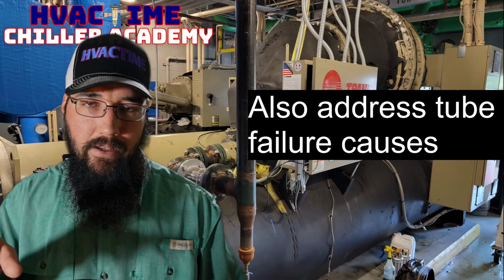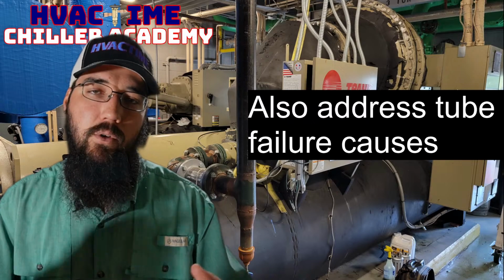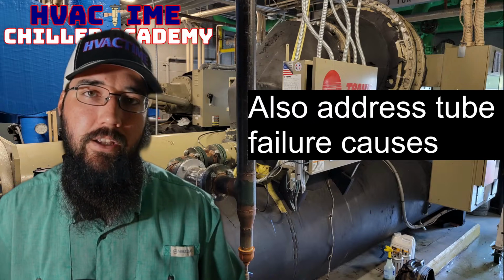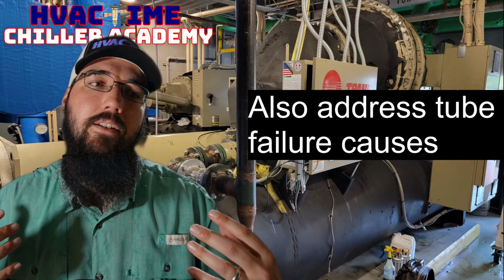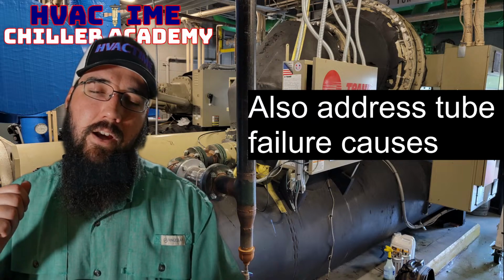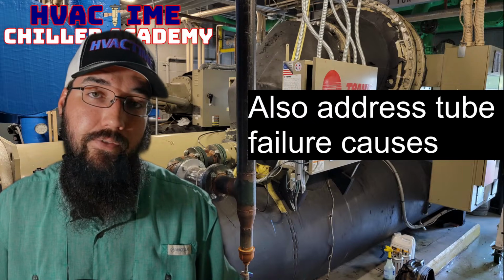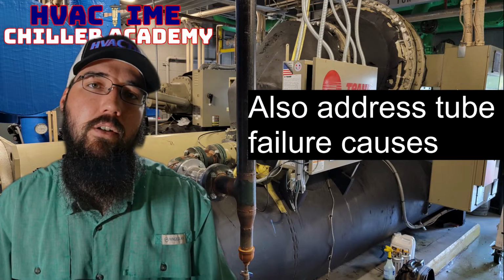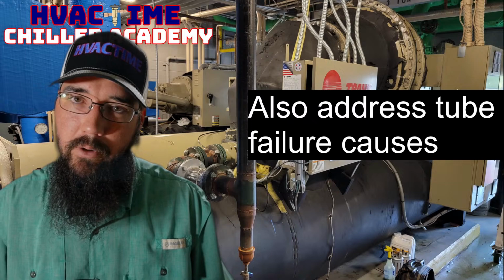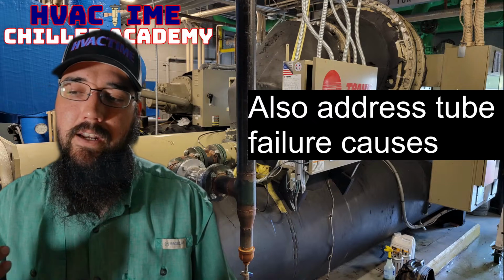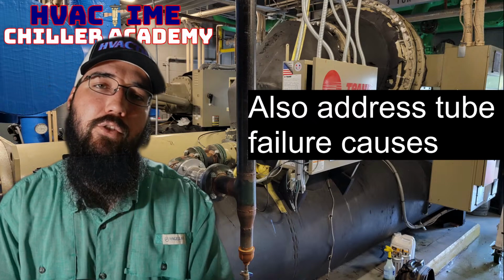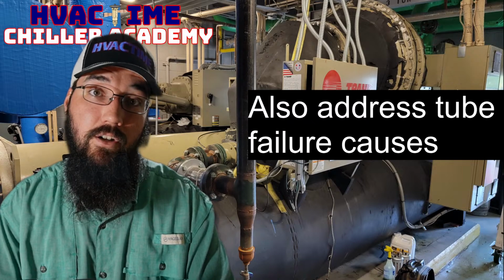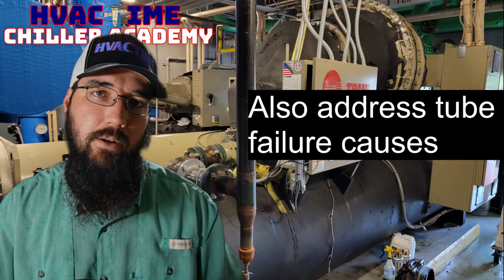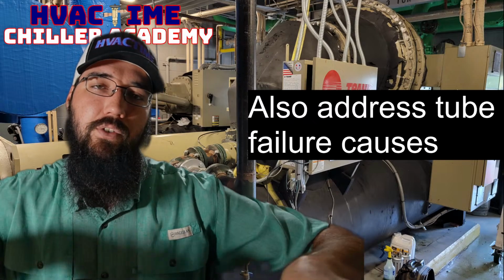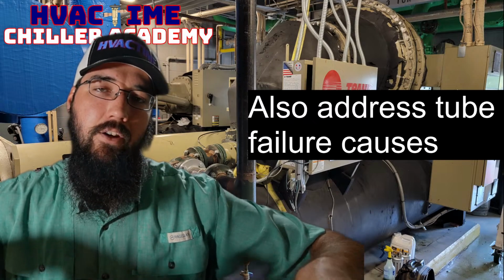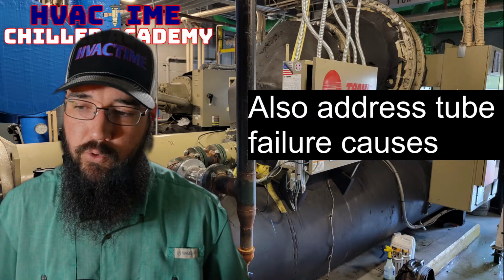And if you had a tube sheet leak where it was leaking at where it's swedged into the end plate, then a lot of the time I've found that doing the plug and putting the plug in the first place is actually enough that it will inevitably seal. Not always, but I found that that is a common way to get one to reseal without having to literally re-swedge it - just putting a plug in forces that swedge to expand out and reseat into the tube sheet itself.